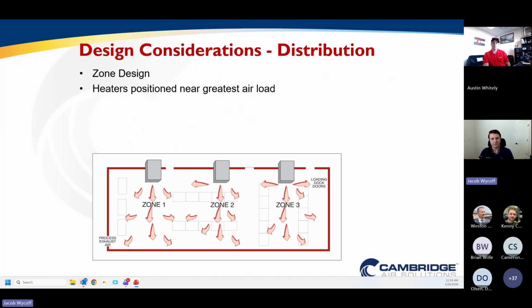Now, if you reach out to Cambridge Air Solutions, we'll run a heat load for your space. We'll help you lay out the equipment. But just so you understand how we typically think about applying these, we're looking more at Zone 1 and Zone 3 designs, mounting the unit near the loading dock doors, blowing it into either large open spaces or through the aisles of the racking, as opposed to Zone 2, blowing it into the side of the racking is not preferred because it's going to disrupt your airflow. But if you look at Zone 1 or Zone 3, that's what's going to give you your optimum air distribution.